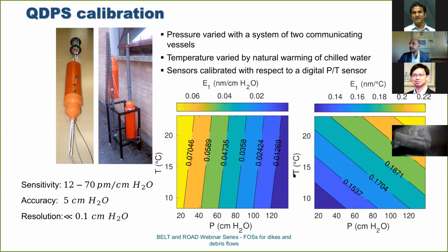We, of course, characterized the sensor in the lab, and we built a particular test case for the characterization. I will not go into the detail of how we characterized the sensor, but I will go directly to the characterization results. Here you can see in the two color maps on the left the response to pressure for one of these sensors, under a varying pressure from 20 to 140 centimeters of water, and from 5 degrees to 27 degrees. The numbers in the color plot refer to the sensitivity, measured in terms of wavelength shift per centimeter of water level variation. And on the right, the corresponding temperature sensitivity of the sensor.